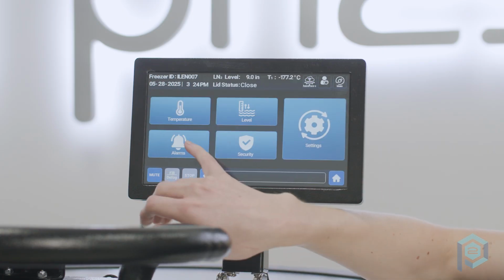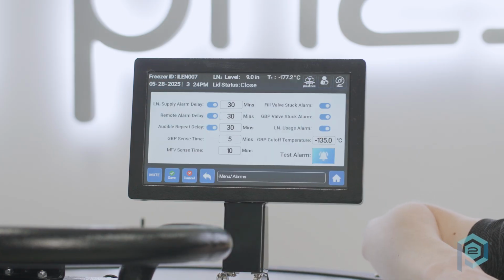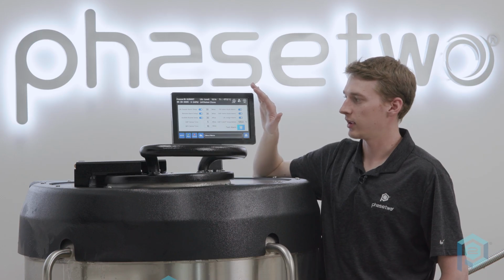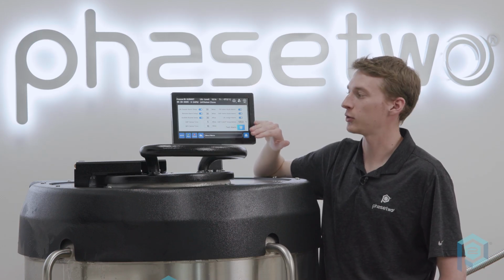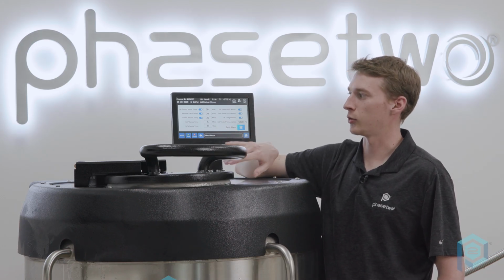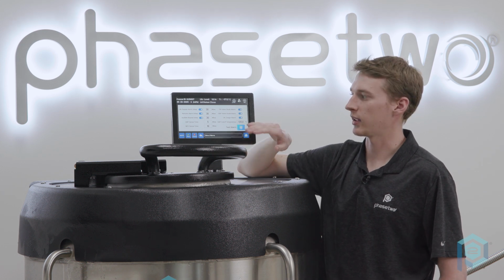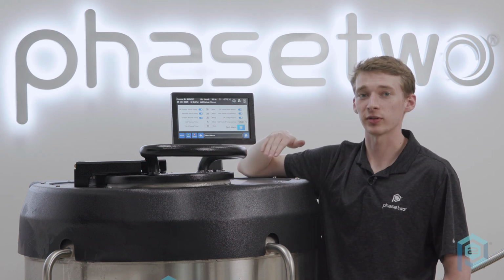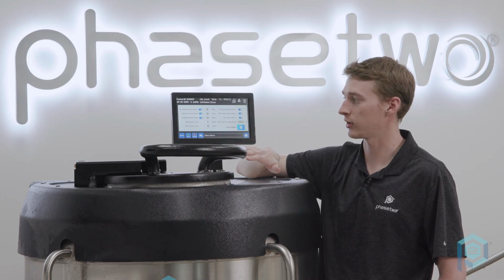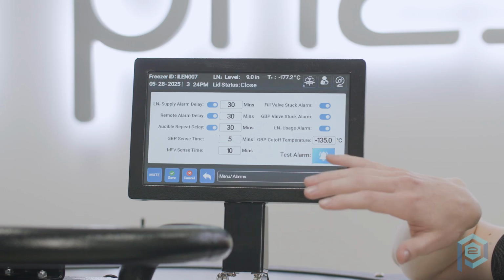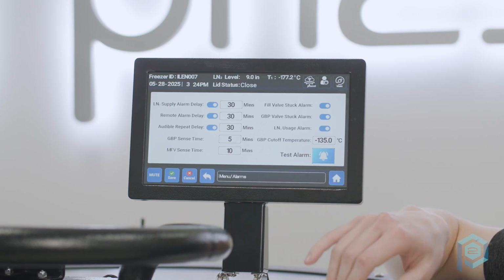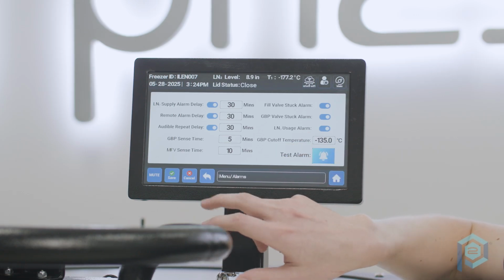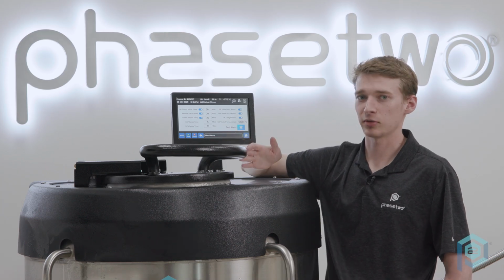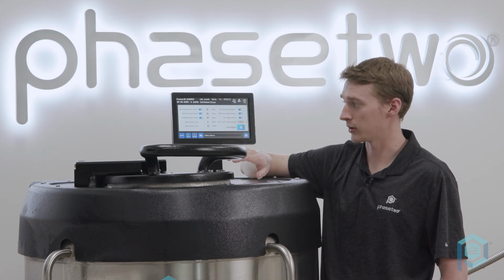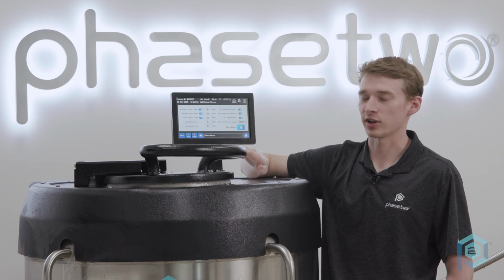So going back to the menu, we now have our alarms page. In the alarms, this is where you can set just about any alarm that you can find in our manual. Big things including LN2 supply alarm delay, how long you want your gas bypass to go until it senses and says, hey, I don't have any liquid here yet, stop the fill, things like that. You're also able to change your gas bypass cutoff temperature, and we can do test alarms as well. So any value, there is a set range for each value, which can be found in the manual, but this is where you would go to make sure you change any of those things.